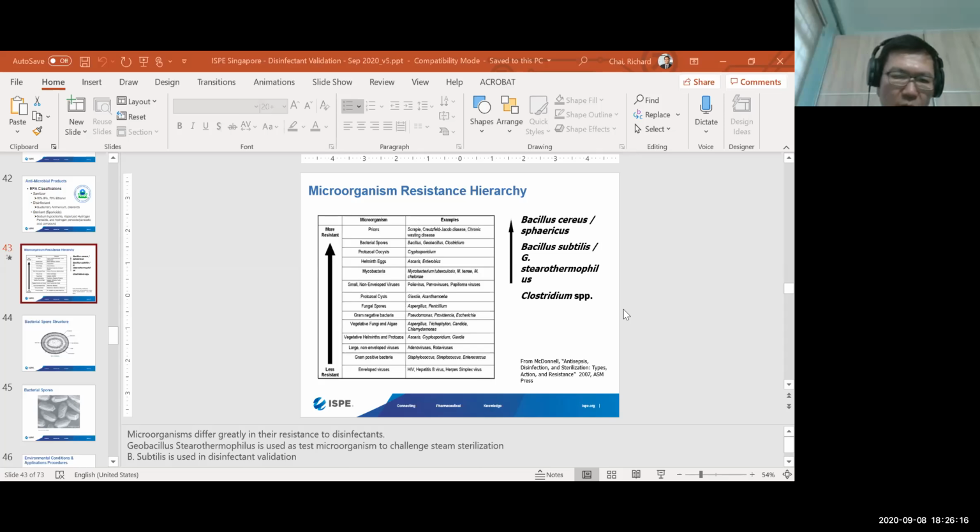Of course, the first one is that you need to have a baseline count monitoring. So you collect the samples on the baseline before any cleaning, and so there's a time 0. Of course you perform the air monitoring, surface, contact plates, settle plates, whatever. That will be very useful information on your baseline. And then you perform the cleaning and disinfection.